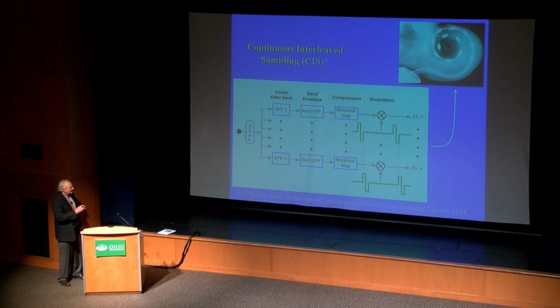So in this strategy, there is a bank of bandpass filters, typically 6 to 12, that divide the frequency range of the sounds we hear across normal frequencies from, say, 50 hertz to 20,000 hertz in normal hearing, into separate frequency ranges. And along the horizontal axis here, you see one of the channels of sound processing. So the first step is to limit the frequency range, in this case to a low frequency range, and in this case to a high frequency range.